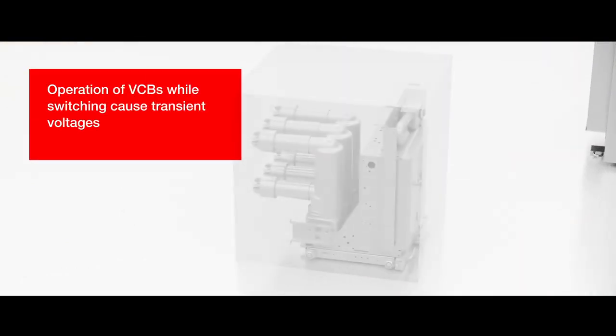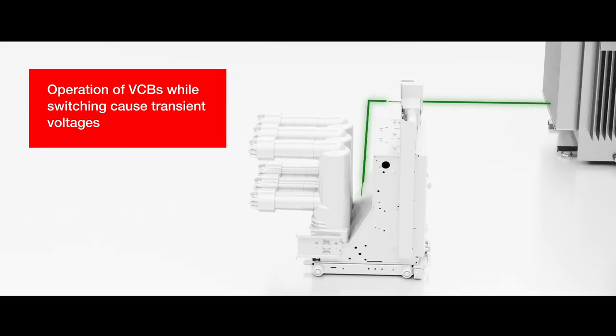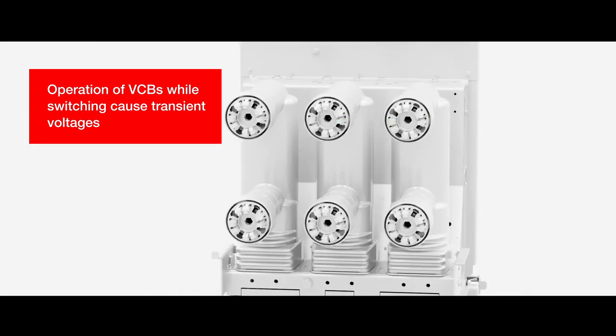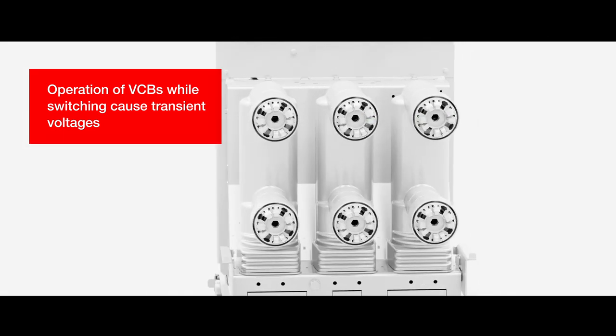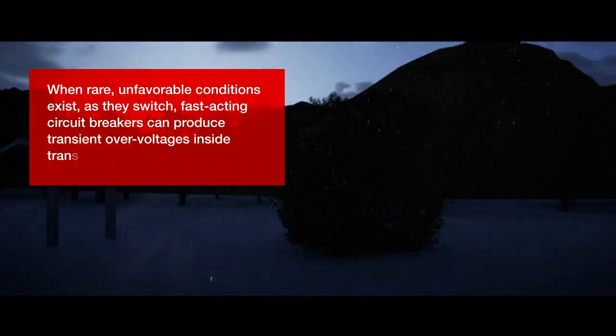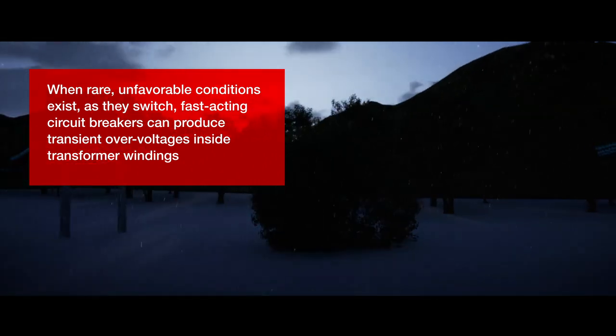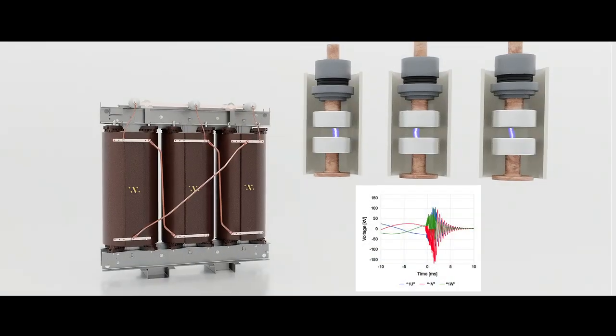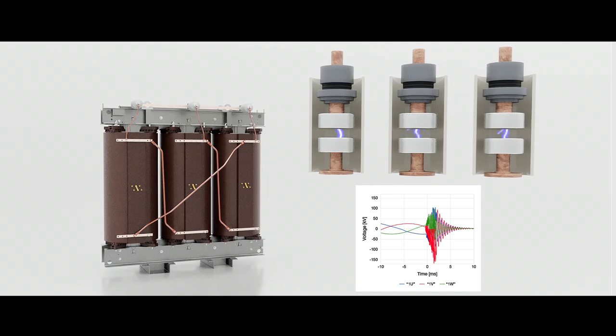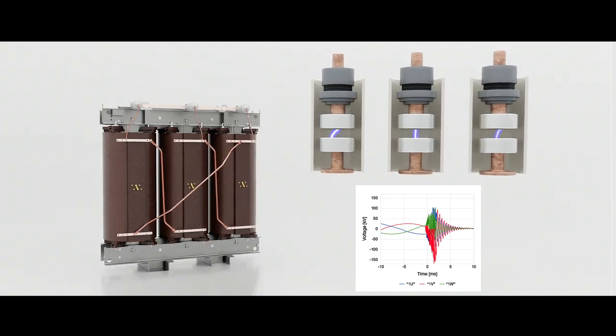These transient voltages occur every time switching happens as the vacuum circuit breakers, VCBs, are operated. In some network conditions and procedural operations, fast-acting circuit breakers can generate transient overvoltages inside transformer windings as they switch.